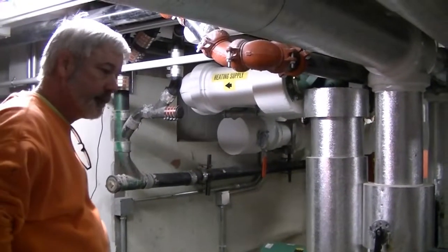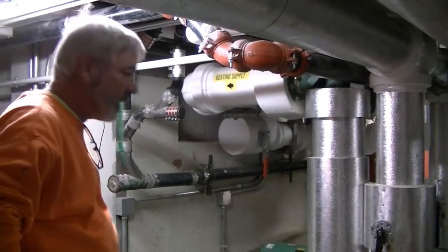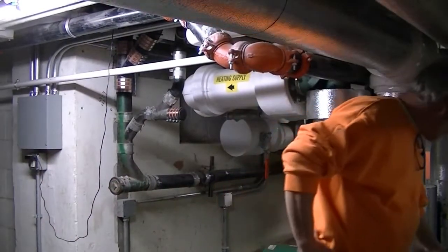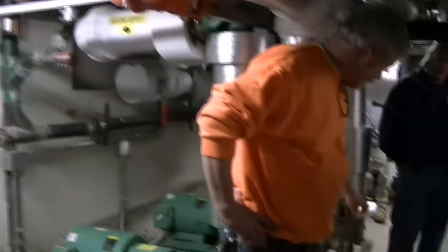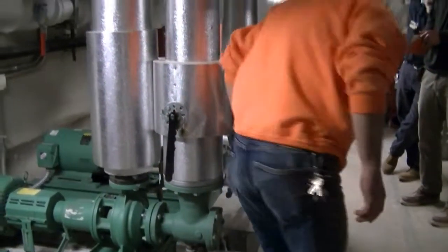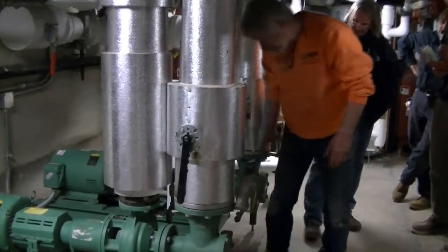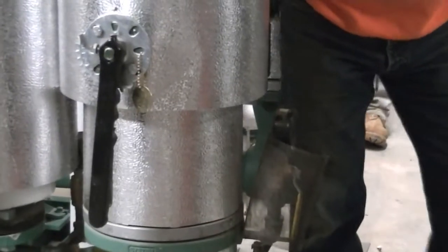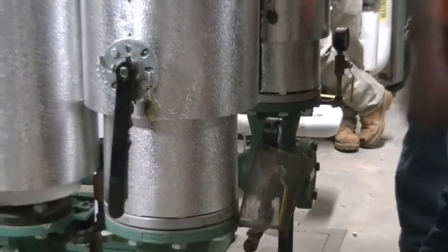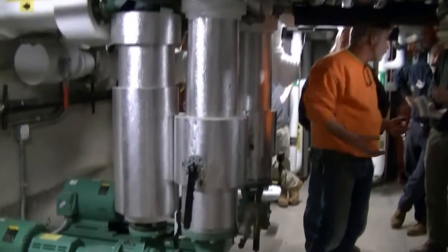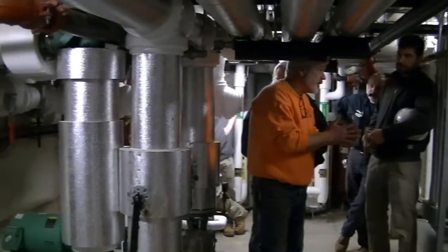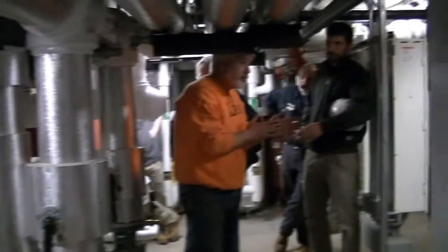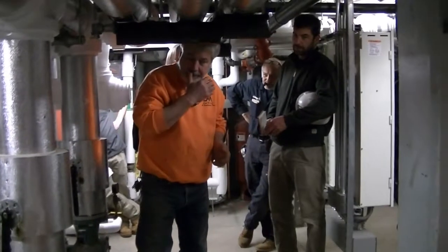Check the suction gauge reading and confirm that it's normal. What's normal? You're going to look at your gauge readings. You have one on the inlet of the suction, and another one on the outlet of the pump over here. You just look to make sure you've got enough water in the system, number one. If you don't, the system is usually going to shut itself down. Water safety is built in, so no pressure. Okay? So what's a normal range?